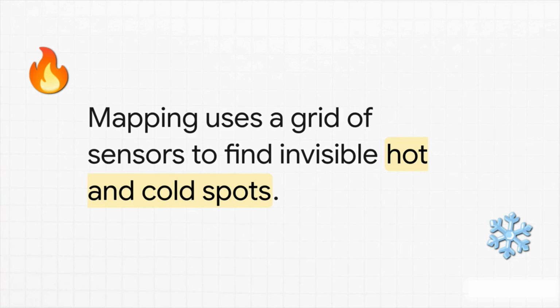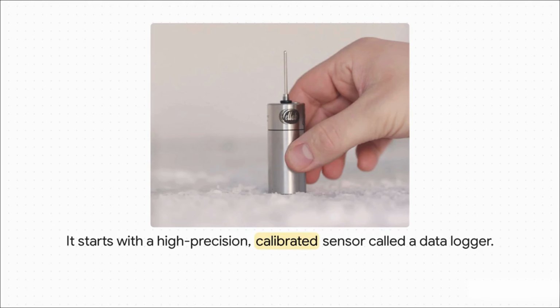See, here's the thing. A freezer isn't one single uniform temperature inside. There are always these tiny variations, invisible hot spots and cold spots. That single temperature display on the outside doesn't tell you the whole story, not even close. To get the real picture, you have to do what's called a temperature map, using a whole grid of independent sensors. The whole process kicks off with this little guy, a high-precision, independently calibrated sensor. It's called a data logger, and it's designed to do just one thing, but do it perfectly. Accurately record temperature over time.